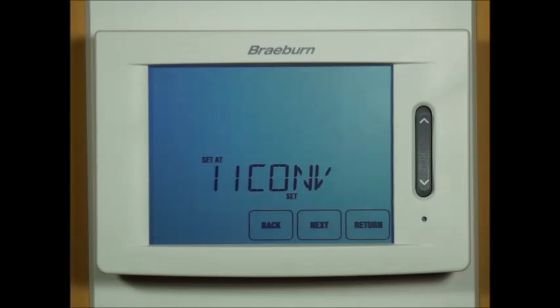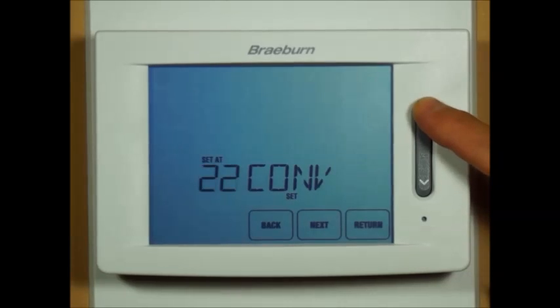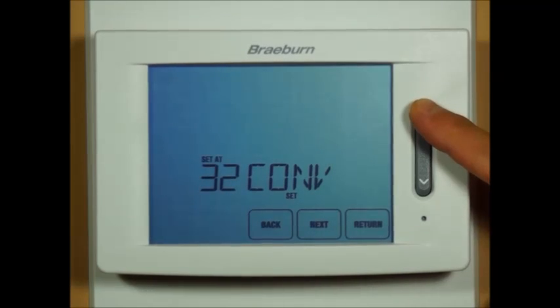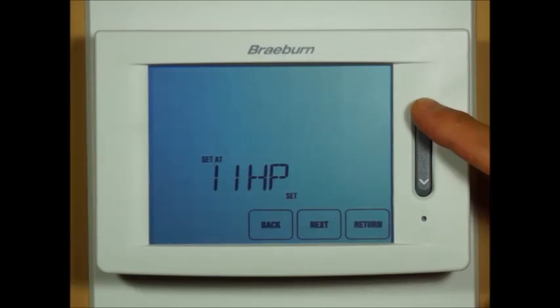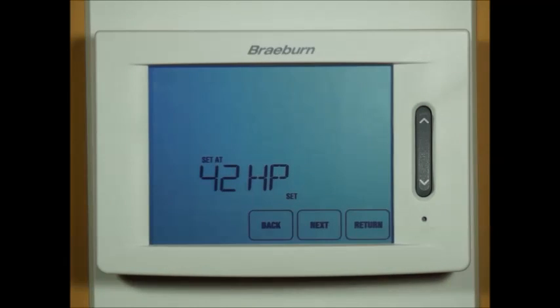This is your system type, where you need to select what type of system you're putting this thermostat on. One heat, one cool conventional is the default. However, you can select two heat two cool conventional, three heat two cool conventional, one heat one cool heat pump, two heat two cool heat pump, three heat two cool heat pump, or four heat two cool heat pump. For this particular demonstration we will leave it on four heat, two cool heat pump.